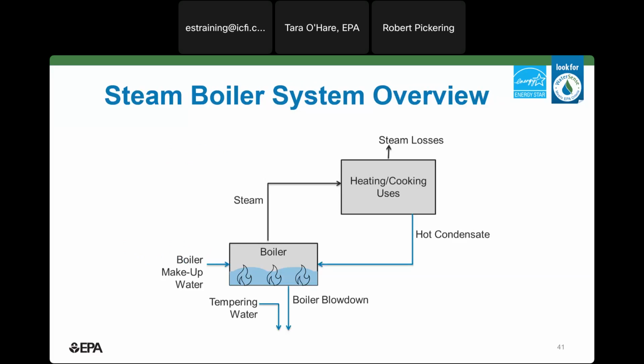So this is a very simple boiler sketch to orient everyone. Steam is produced in the boiler and used for either space heating or potentially other uses. Once the steam gives up its heat, it condenses back to water and is often collected and returned to the boiler. Similar to cooling towers, over time, minerals can build up in the boiler and periodic blowdown is required to remove them from the system.